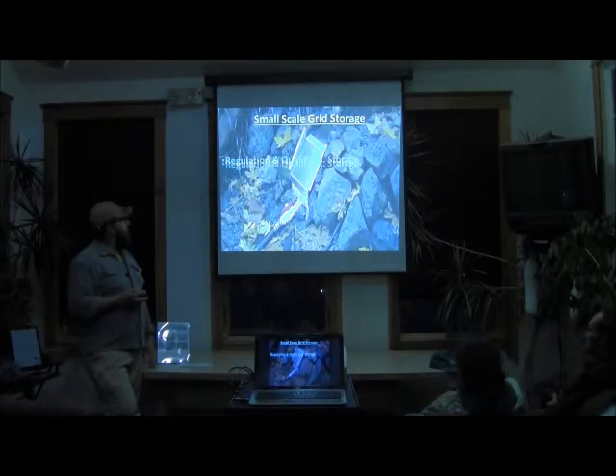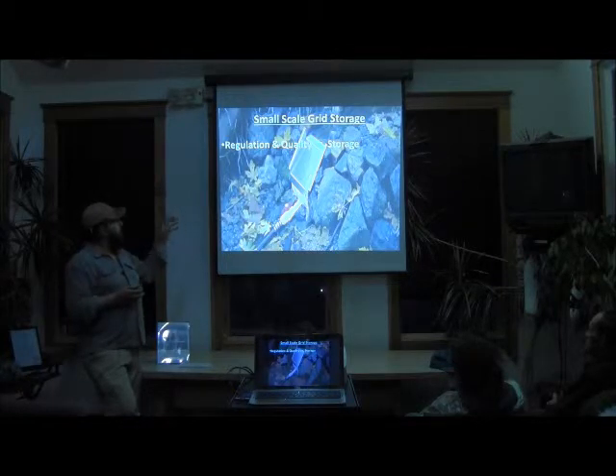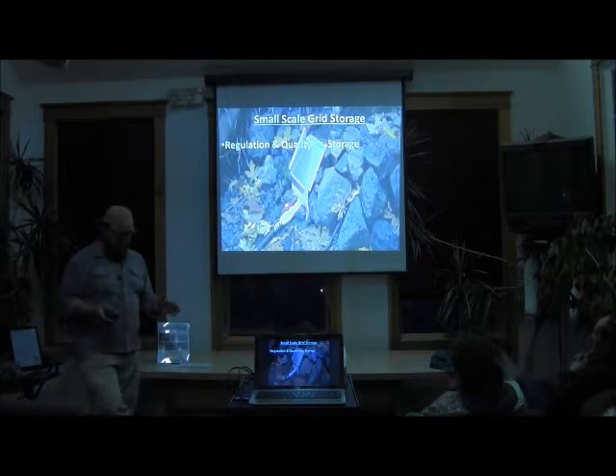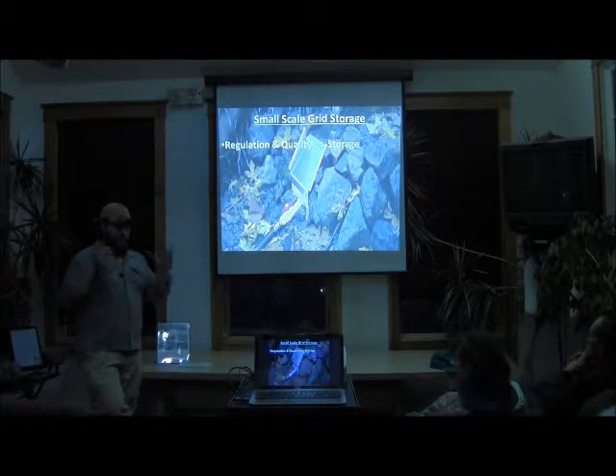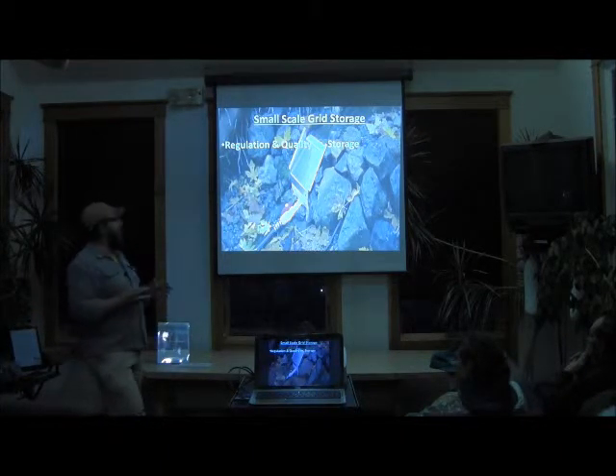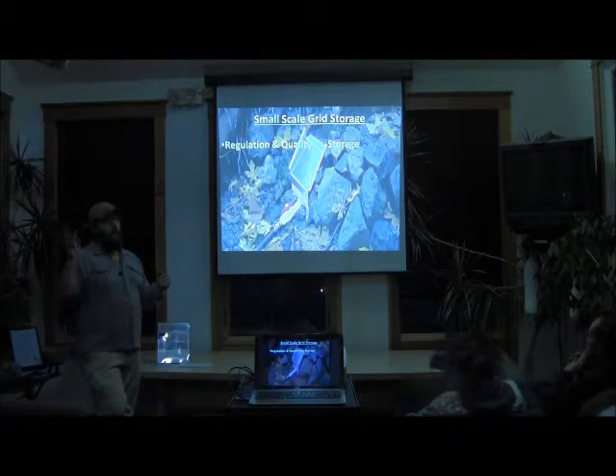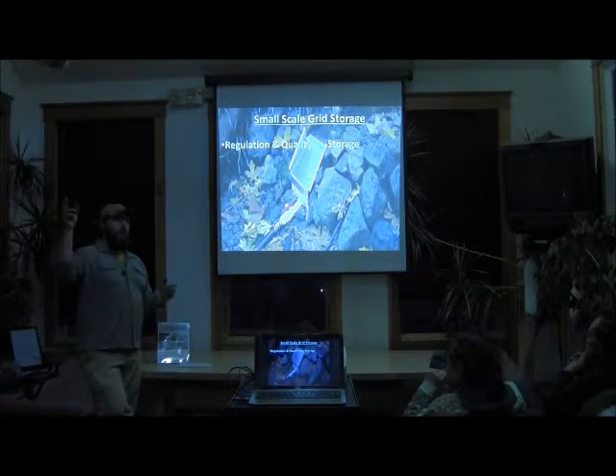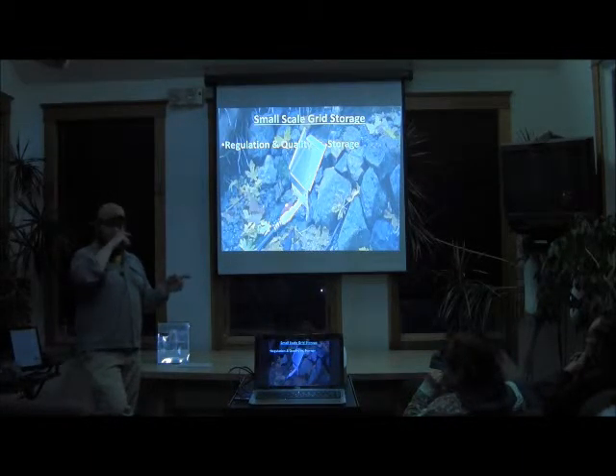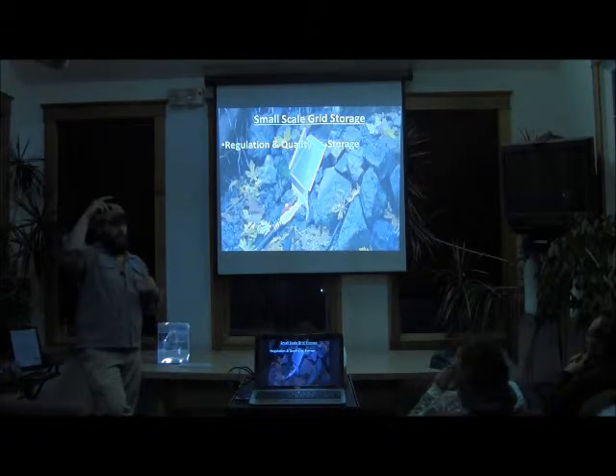All right, small grid storage. When we look at grid storage, there's two things: regulation and quality, and I won't get into this too much because it would take a long time. It's a concept I have trouble understanding all the time. Regulation, quality, and storage. In the summer at our Powder Creek plant, even though it's rated for 6.3 megawatts, we only run it at 5,800 kilowatts when there's enough water available because we need a buffer. We have a 500 kilowatt buffer.